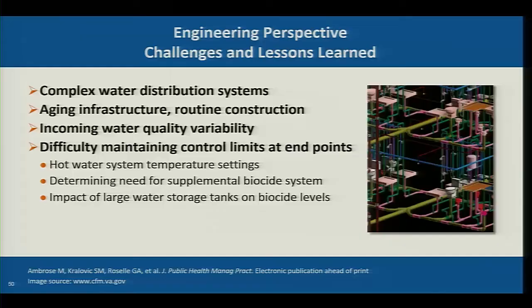These are some of the engineering challenges our facilities have had to deal with. The first three challenges may be difficult to address or change, but understanding them is important for decision making. The last arrow bullet highlights things that may be learned by facilities as they try to optimize implementation of control measures throughout their buildings. Optimization may require adjustments for how hot water temperatures are implemented or how biocide residual can be maintained. And it may require assessing water system components such as on-site large water storage tanks and how that affects biocide levels at the tap. These are real-world issues that may not be obvious when first drafting a prevention plan.